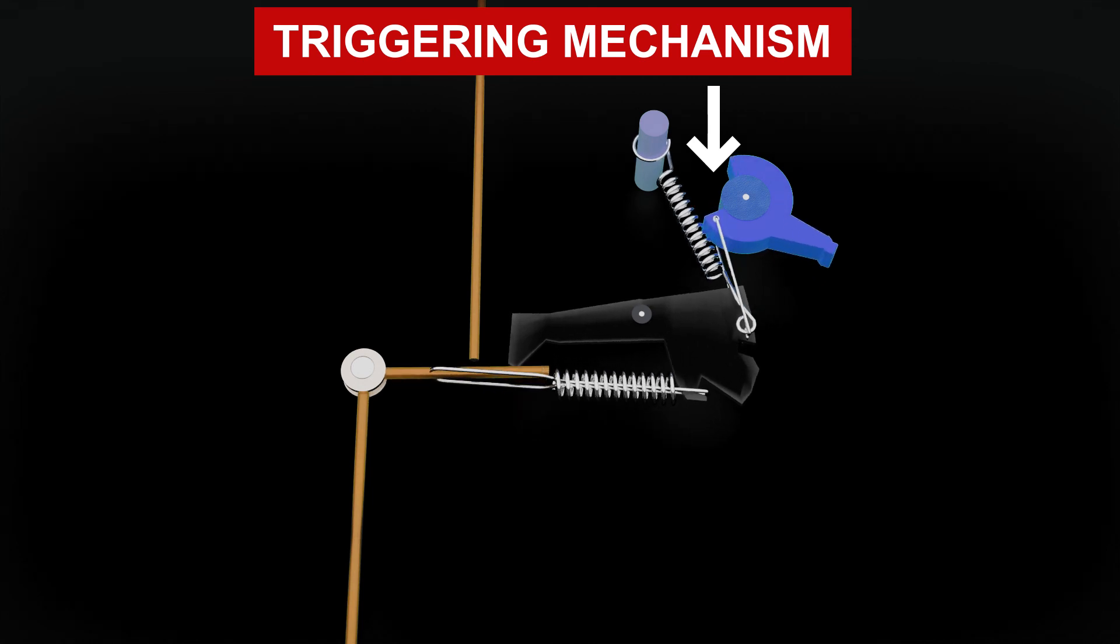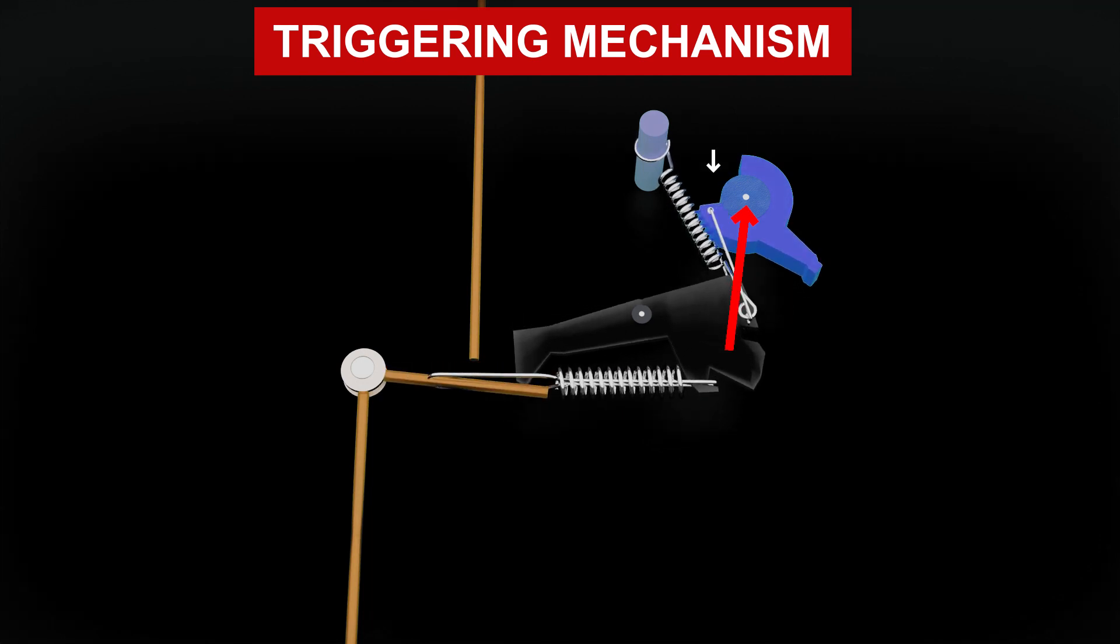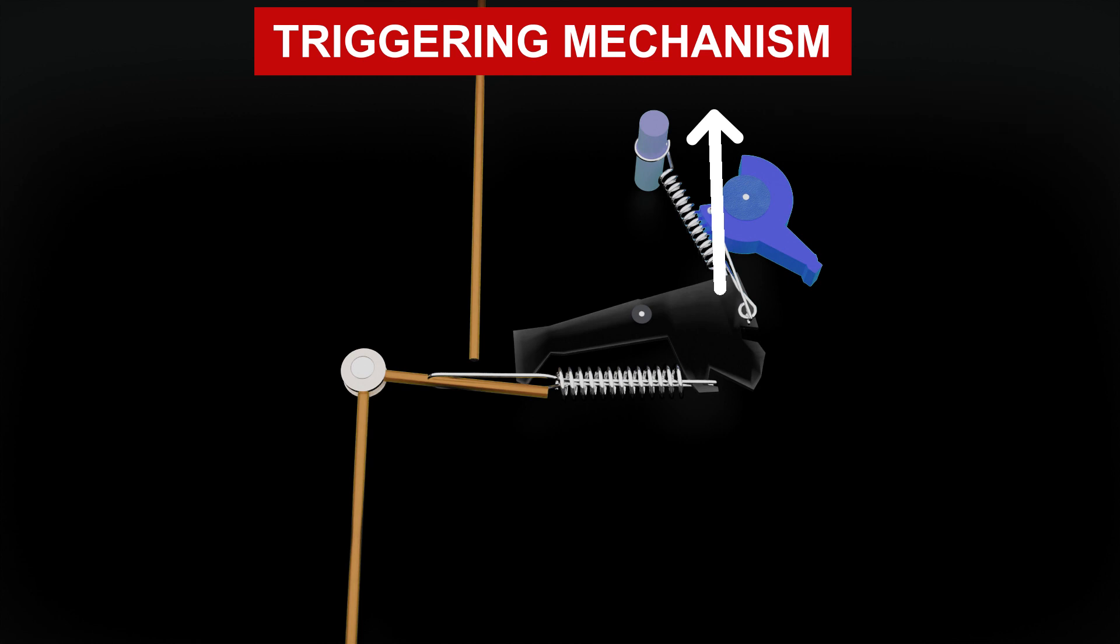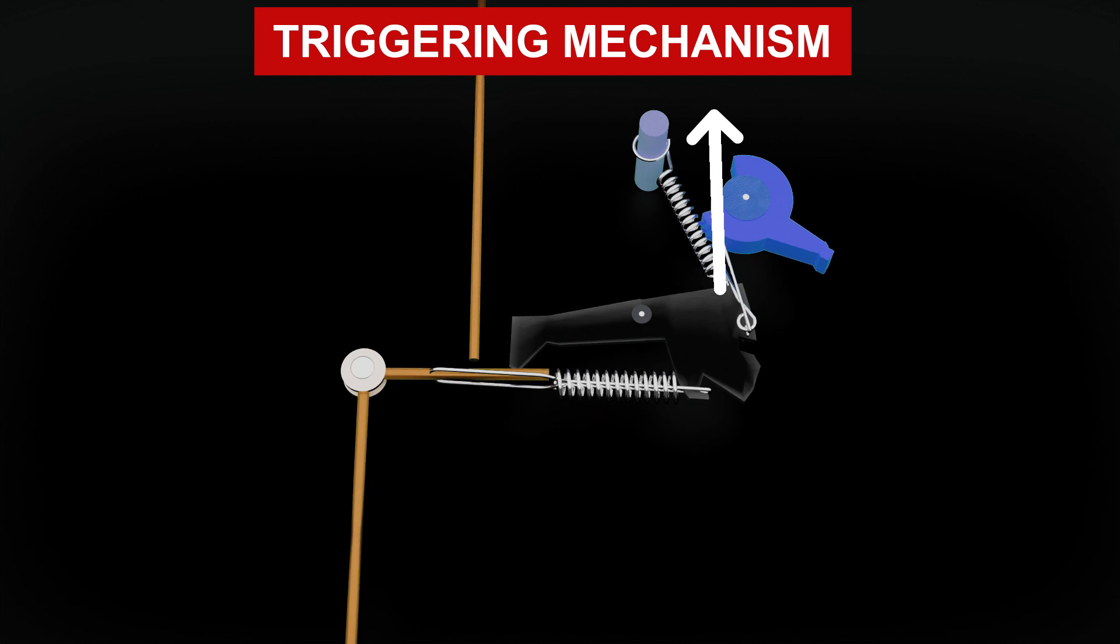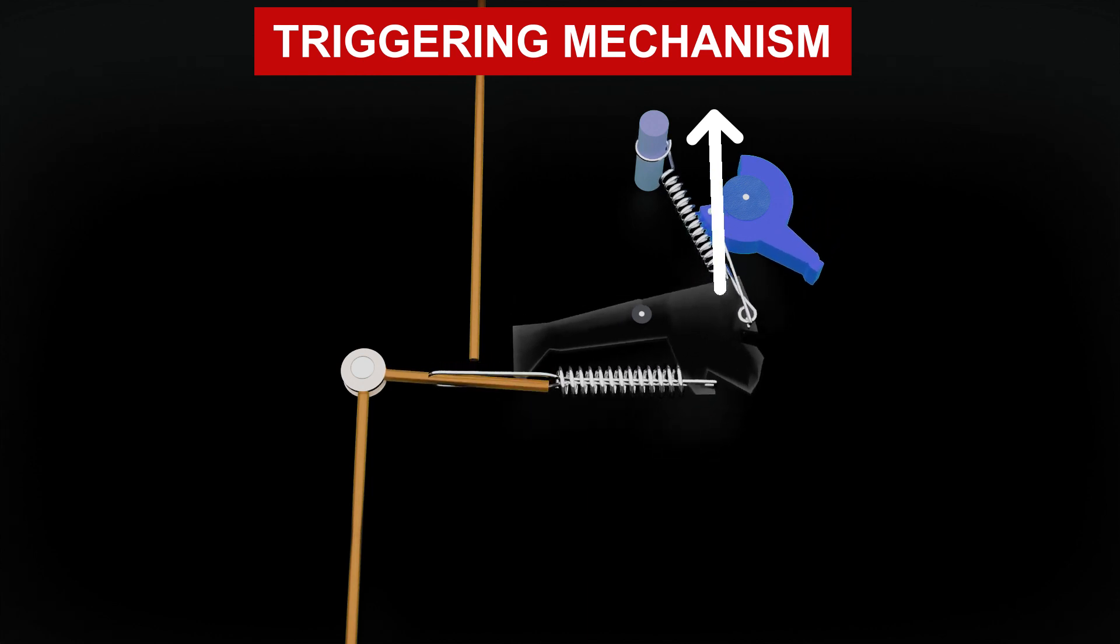The resultant force of this spring and the downward force of the lever are in opposite directions. The resultant force of these two forces is called the offset force. If the direction of this offset force is to the left of the center of the main lever, a clockwise torque will be produced on the lever which will move the lever down.